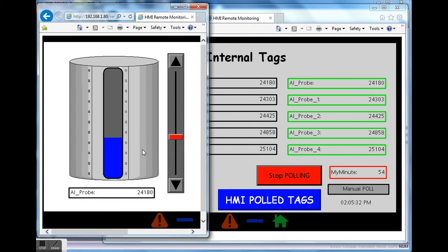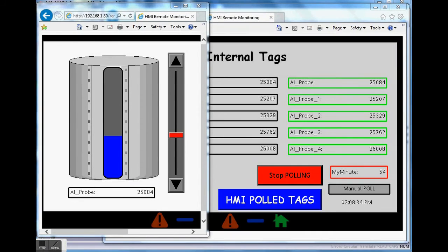If I go back to the page and show the data logger, it's okay when I go up to 32,767, but when I roll over that number, say here I've got 35,000 as the raw number coming in, Red Lion makes it a signed integer and starts to go from negative 32,000 back down to 0. Watch, when I get all the way to the top, I'm all the way at 0, but really I'm going 0 to 65,535 here, as you can see. So that posed a little bit of a problem for me.